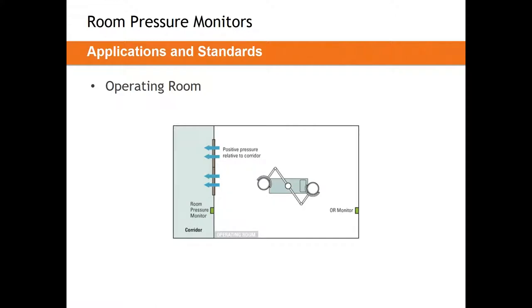If you have multiple doorways, some operating rooms do have two entrances. If both spaces outside the OR are neutral, it may be advisable to only measure pressure in one location — if you're trying to measure the same physical quantity twice, you will get slightly different measurements. However, if one corridor is neutral and the other is slightly more positive or negative, it is perfectly acceptable to monitor pressure in both locations.